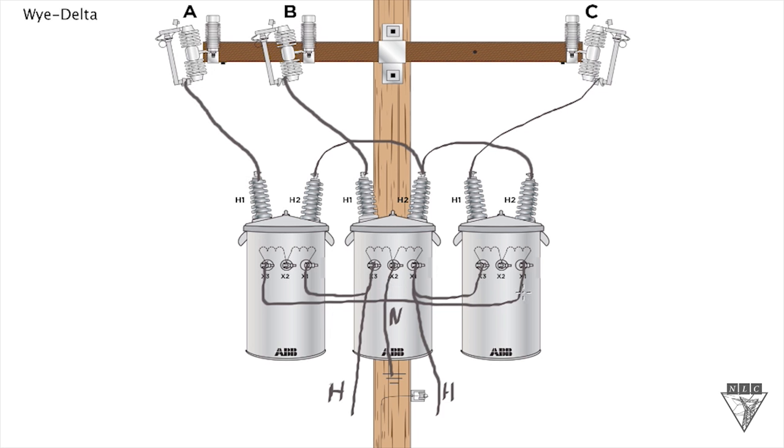Your last connection is going to be your power leg. The way you identify your power leg is it's one and a half coils from the neutral. So what I mean by that is we've got one full coil in this transformer, half a coil in this transformer until you get to the neutral. So this power leg right here is one and a half coils away from our neutral. That's how you identify your power leg.